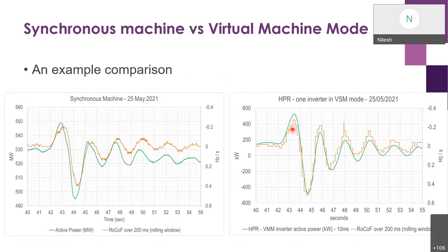And in the next slide, I try to compare, as an example, the synchronous machine response on the same day versus the response from one of the inverters. Again, the same concept. On the right hand side, the left axis is the kilowatt, I would say kilowatt, from the inverter in a grid forming mode. Y-axis, again, inverse y-axis, and the calculation is the rate of change of frequency on a 200 millisecond rolling window.